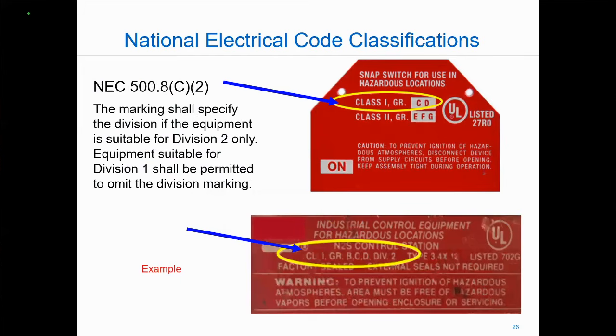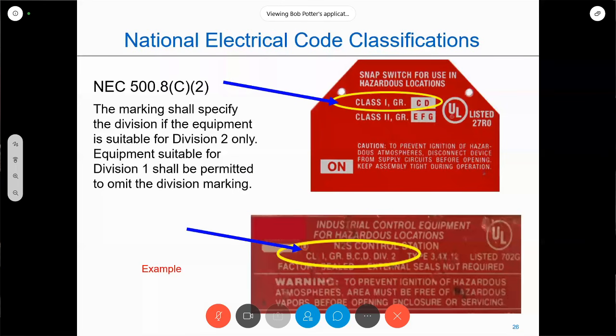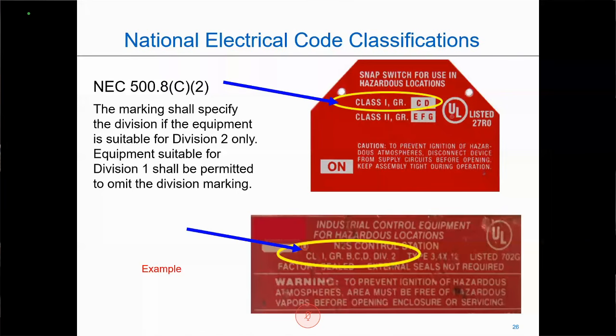Now, there are times that you may see a nameplate that does not signify division. The top pictorial that you see there is a perfect example of that. It just says Class 1, and then it has the groups that this particular piece of equipment has been approved for. Whenever you see a nameplate that says Class 1 and does not signify a division, it is approved for Division 1. Technically, the code only requires you to mark a product for Division 2. So you see the bottom pictorial has our class, it has our division, and it also contains the groups that that particular product has been approved for.